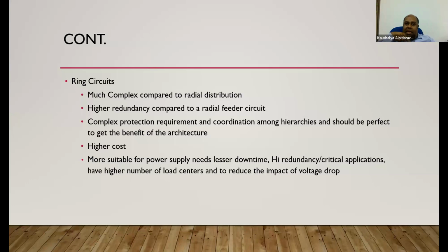A ring circuit forms a ring from the secondary substation back to the secondary substation, and your load centers are connected either through this ring or a tap off from the ring as a radial. So this involves much more complex protection schemes, and it is highly redundant because a particular load center can be fed from two directions. It is costly and more suitable for environments where you need lesser downtime and high redundancy, critical applications, or applications which have a higher number of load centers.